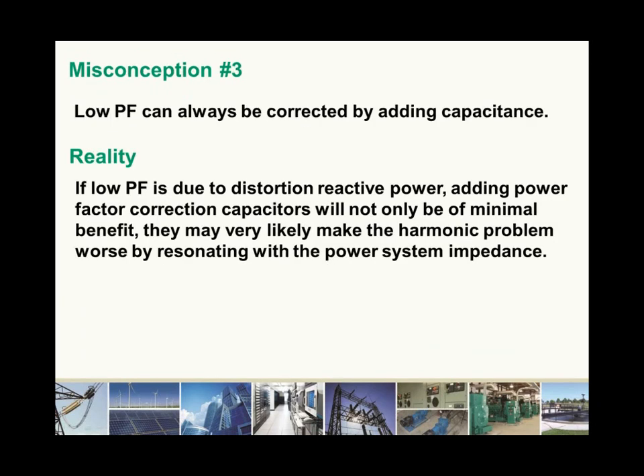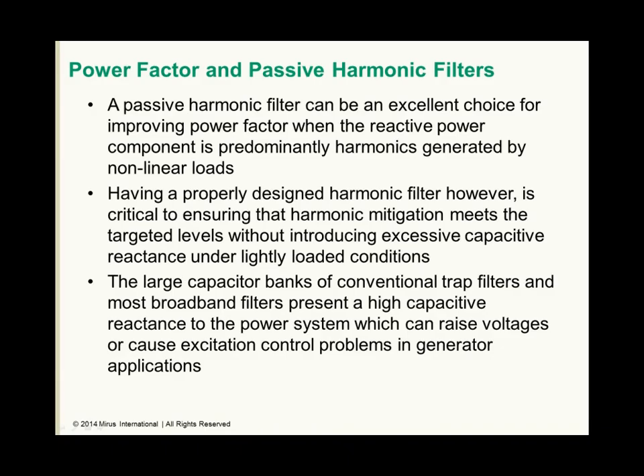So misconception number 3 is that low power factor can always be corrected by adding capacitance. In reality, if low power factor is due to distortion reactive power, adding power factor correction capacitors will not only be of minimal benefit, they may very likely make the harmonic problem worse by resonating with the power system impedance. But one solution that can be effective in improving power factor when we have a lot of nonlinear loads is passive harmonic filters.